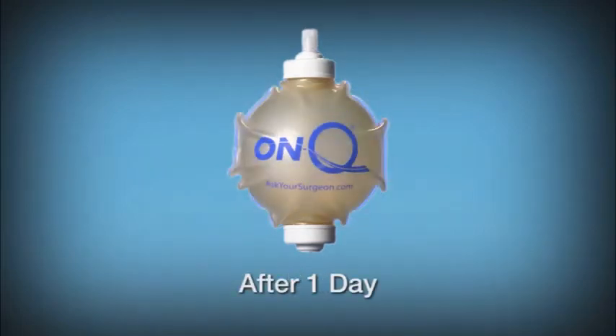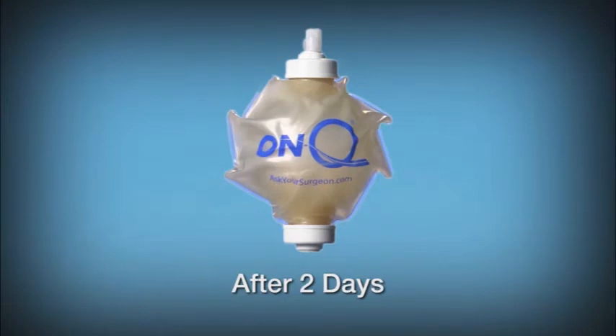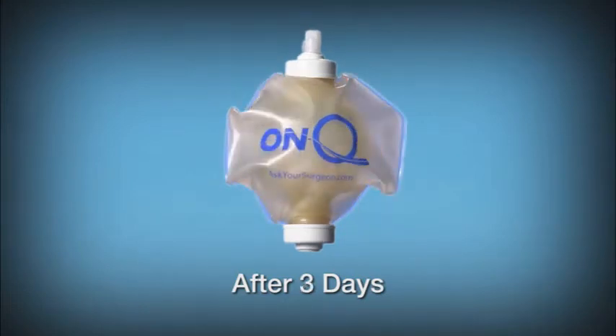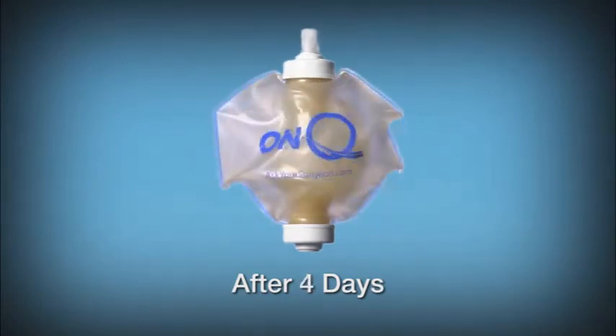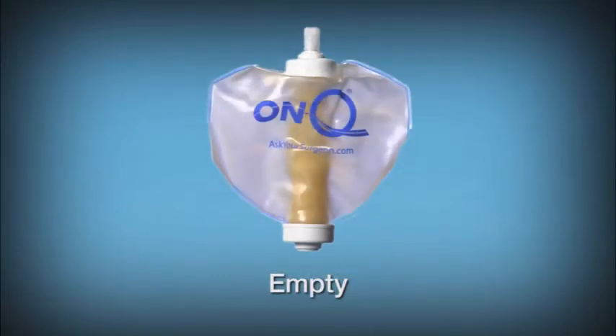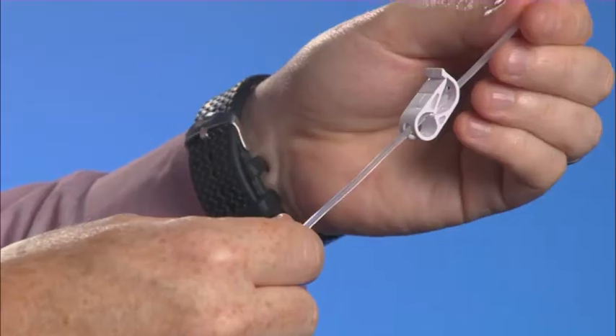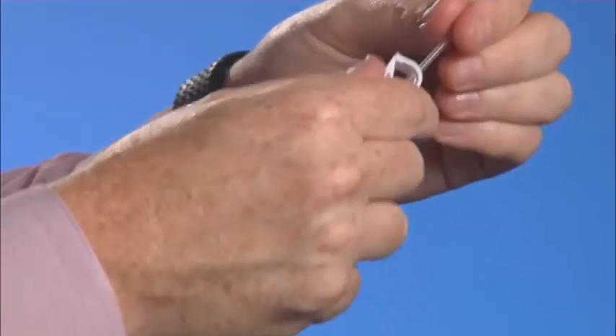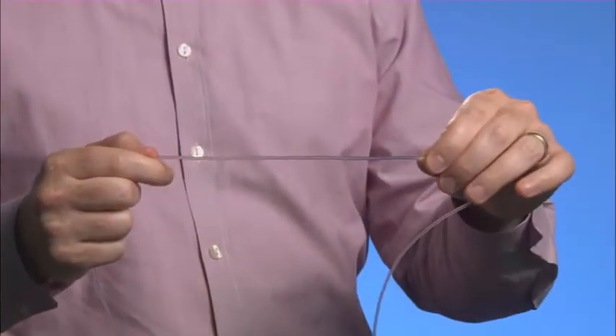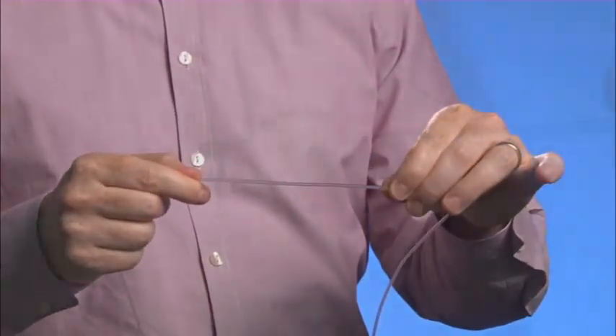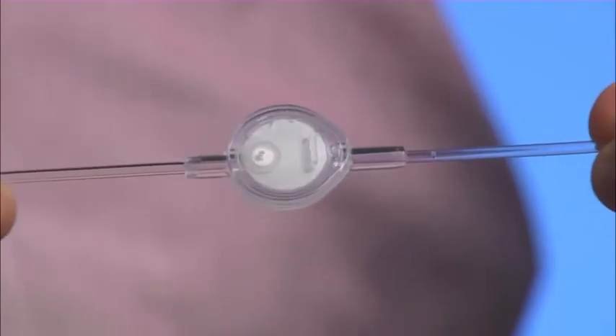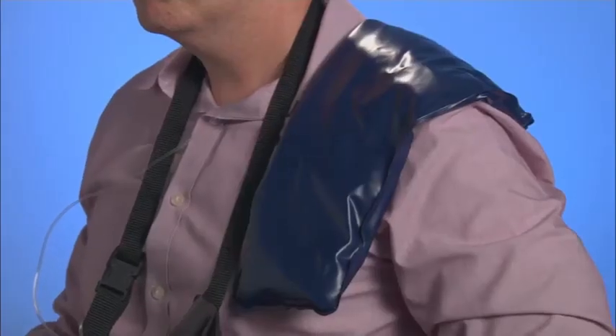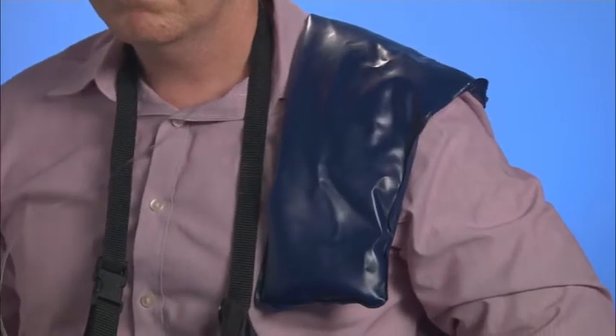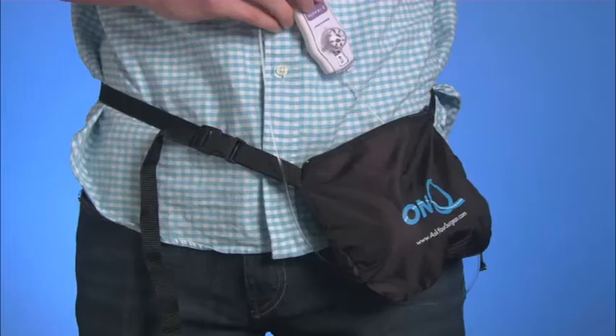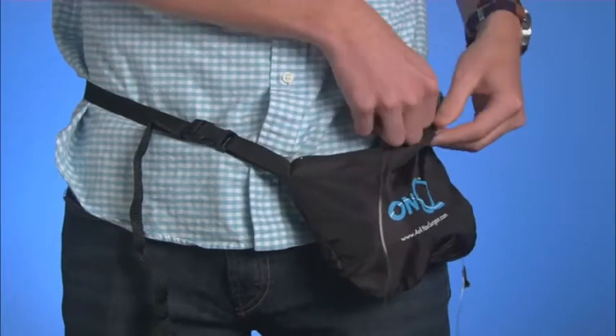As the medication is delivered, the pump ball will gradually become smaller. In time, the outside bag on the pump will begin to get looser and wrinkles will begin to form in the bag. The pump's appearance may vary depending on the size and flow rate of your pump. Make sure the white clamp on the tubing is open and moves freely on the tubing. Make sure there are no kinks in the pump tubing. Do not tape or cover the filter. If you are using ice or cold therapy, place it away from the lower part of the pump tubing that contains the flow controller. Make sure to keep the SelectaFlow outside your clothing.